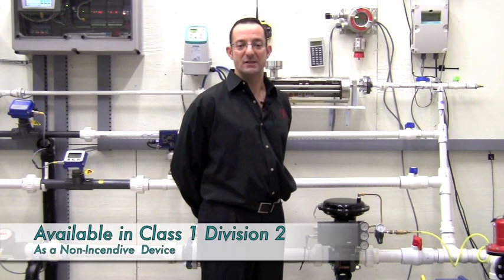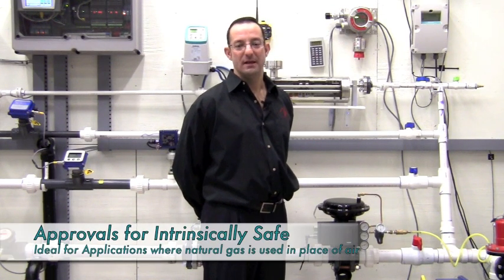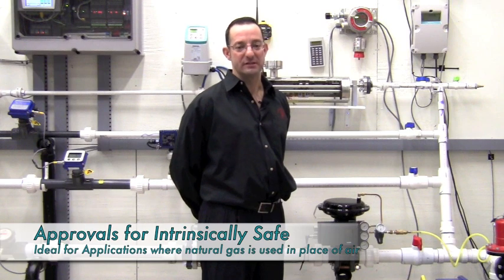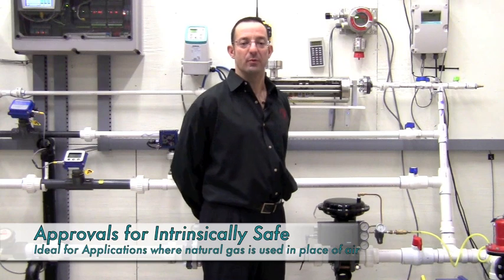The PS2 is available in Class 1 Division 2 configurations as a non-incendive device and also has approvals as intrinsically safe, including applications where natural gas is used instead of compressed air.